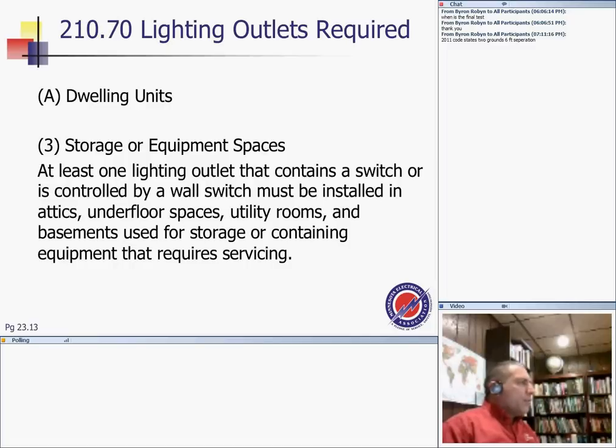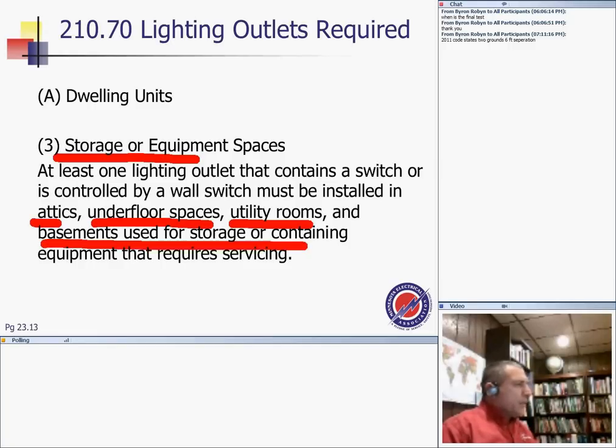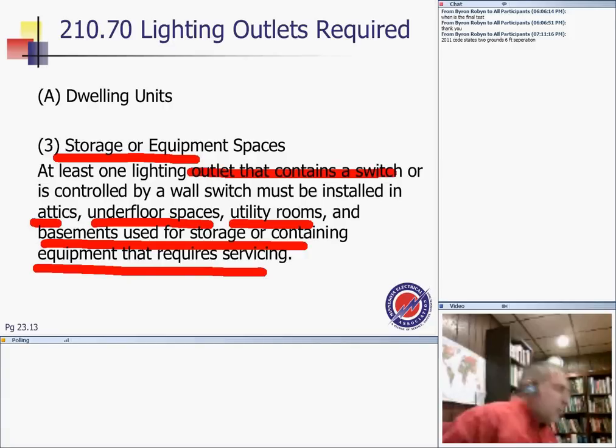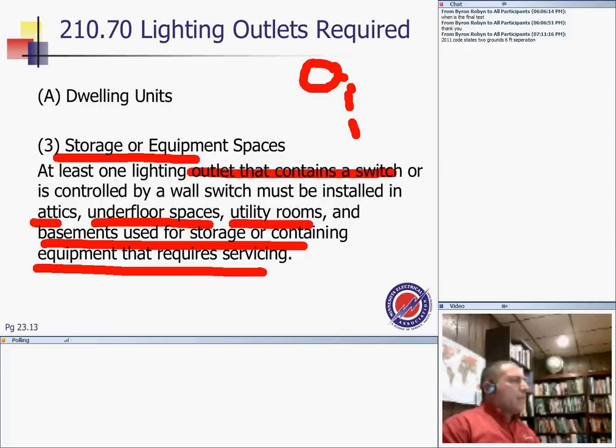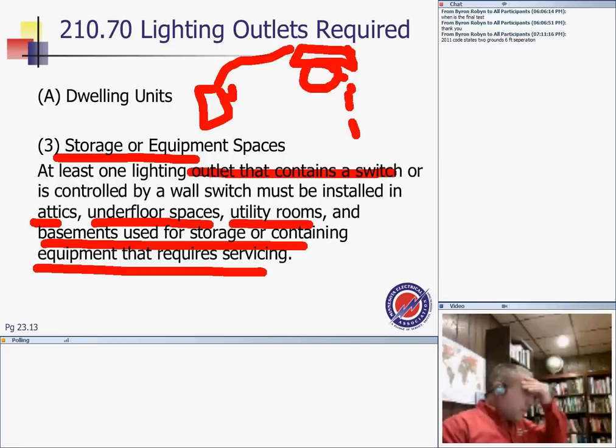In some spaces, at least one lighting outlet controlled by a wall switch must be installed: in the attic, underfloor spaces, utility rooms, and basements used for storage or containing equipment. So at least one light outlet that contains a switch. The light could be a switched lighting fixture, or it is controlled by a wall switch. In the basement, you can have the lighting fixture right there with the little switch that you can switch, or you can have a switch on the wall switching the fixture. Either way.